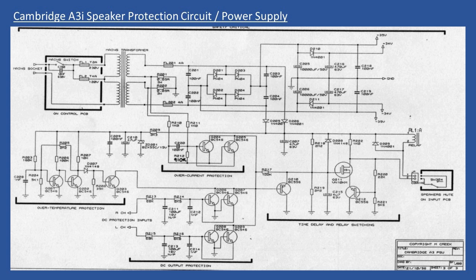Now some relays, as you can see on the different relay types, are transparent and you can see through them, and those relays are not sealed as such, the same as the example that I'm showing you on the 2 relays that were removed. When I say they're not sealed, it's not a vacuum inside, so you have air in there, oxygen in there, and electricity and oxygen over time creates this oxidization on the relay contacts.